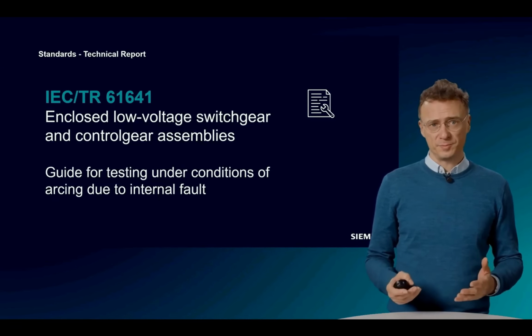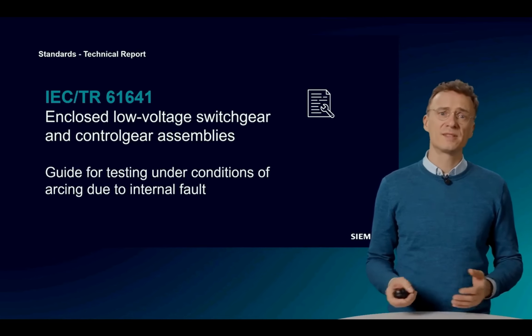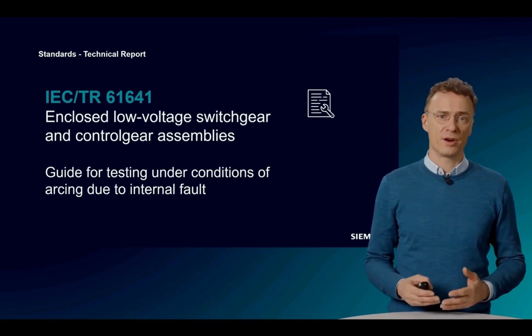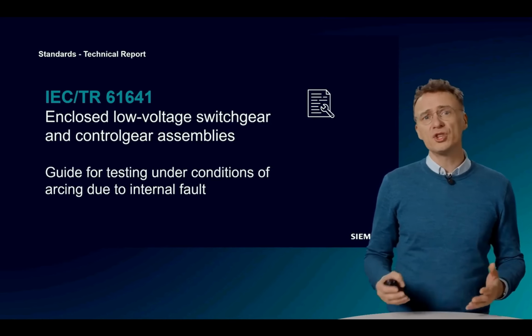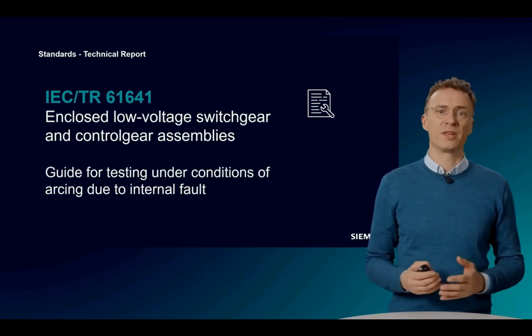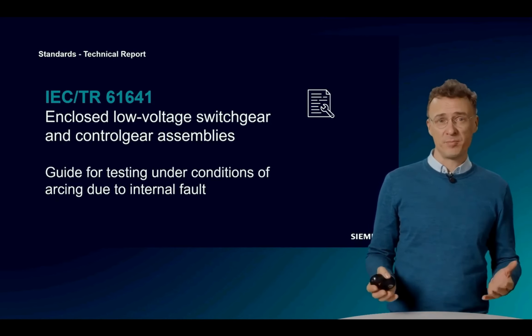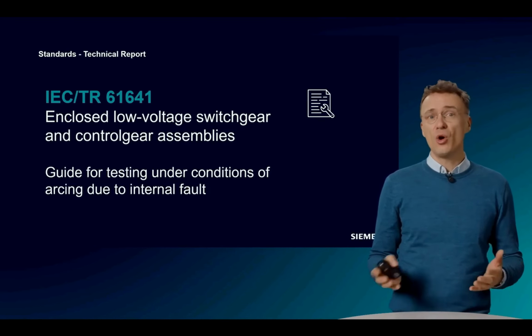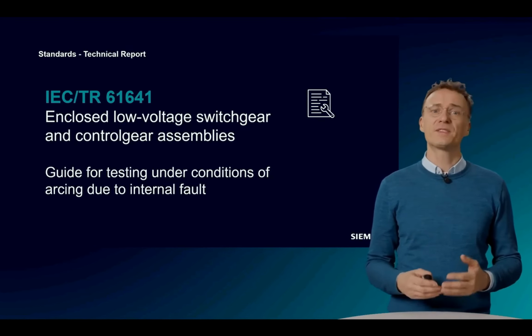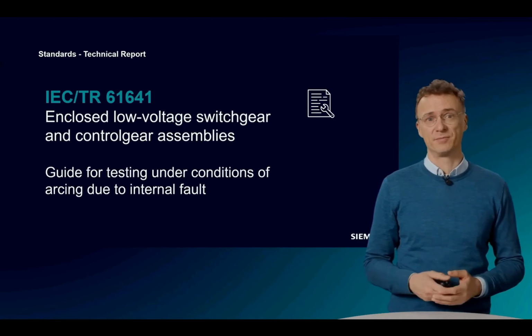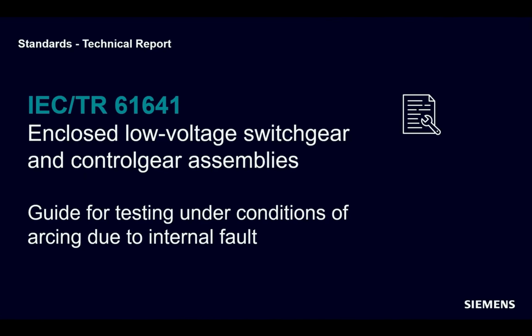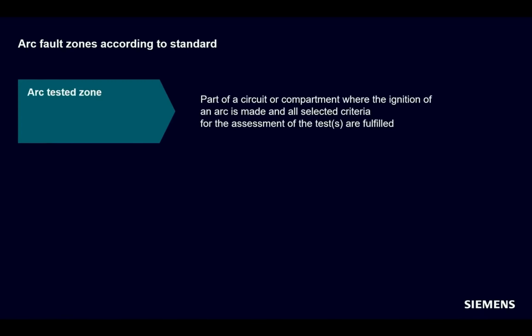These include voltage, currents, and the burning time of the arc, but also features such as who has access to the assembly. Everyone, that means unrestricted access, or only authorized personnel. This corresponds to restricted access. The proof of arc fault protection can be carried out in two different ways. On the one hand, by testing. In this case, there's an arc tested zone.